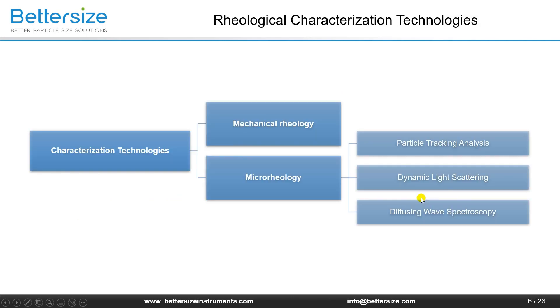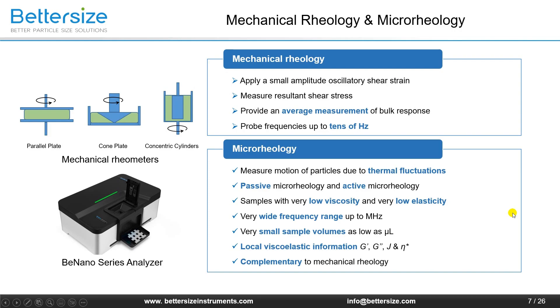What instruments should we use to measure rheological properties? We can divide measurement technologies into two types. The first is conventional mechanical rheology, which is still widely used — for example, a rotational rheometer that compresses the sample and applies rotational shear to deform it. However, microrheology techniques have been developing more rapidly. There are three types of microrheology research methods: particle tracking analysis, dynamic light scattering, and diffusing wave spectroscopy. Mechanical rheology involves applying small amplitude oscillatory shear strain and measuring the resulting shear stress, providing an average bulk response measurement, but it can only probe frequencies up to a few tens of hertz.